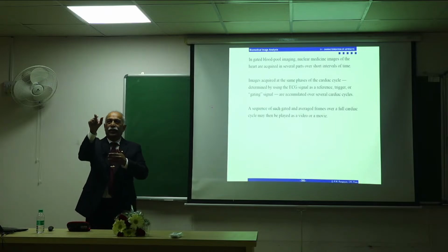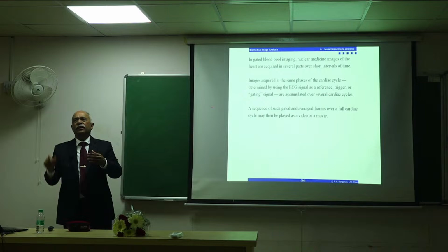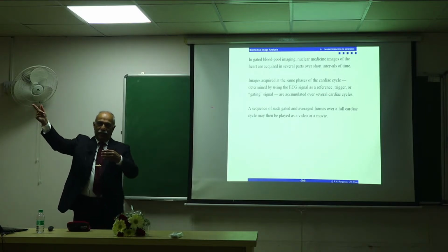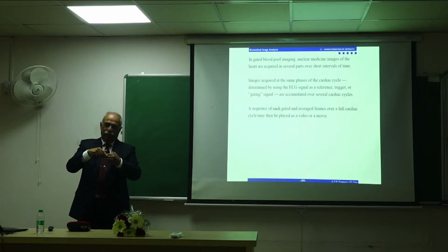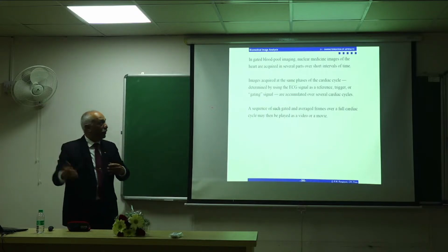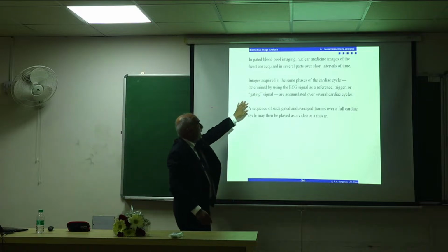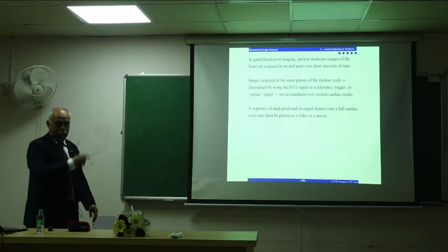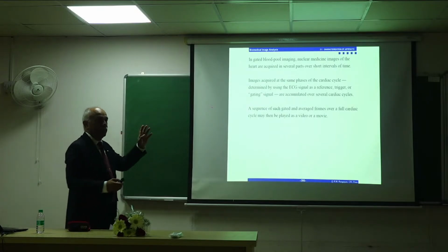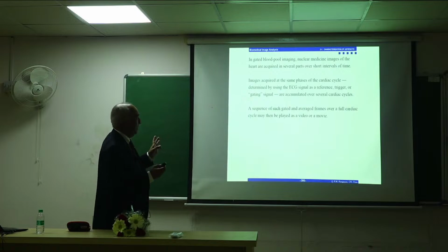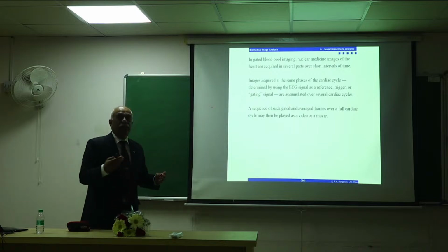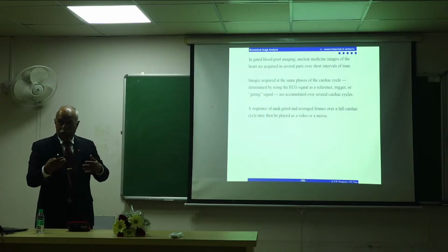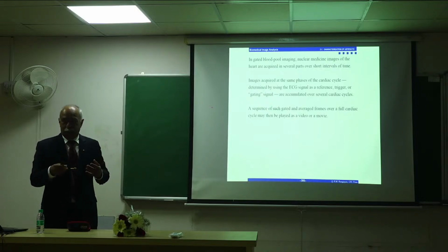So the next window you put in the next frame, and maybe you take 8 or 10 frames per cardiac cycle. And when the next first heart sound comes, or the QRS complex comes, you put that to the first frame, second frame, and so on. So this is called gated imaging, using the ECG as a gate. So this takes benefit of cyclostationarity. Otherwise, it's not possible to get a picture of the heart using an imaging system that requires counting of photons over several seconds.